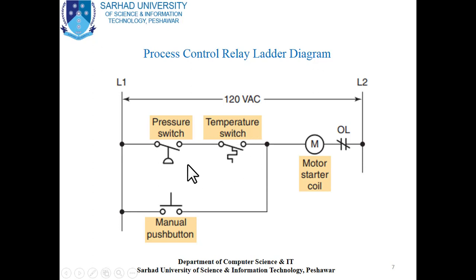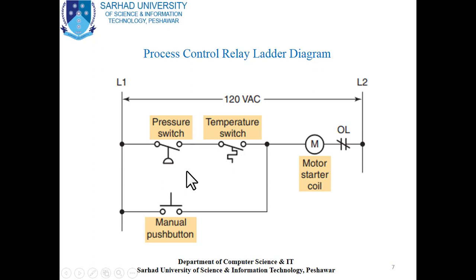Here you can see the two sensors: the pressure sensor and the temperature sensor, each with their respective schematic symbols — which are totally different from each other. The manual push button is normally open. The pressure switch is also normally open, and the temperature switch is also normally open. Each input has two terminals: for the pressure switch, terminal 1 and terminal 2; for the temperature switch, terminal 1 and terminal 2.